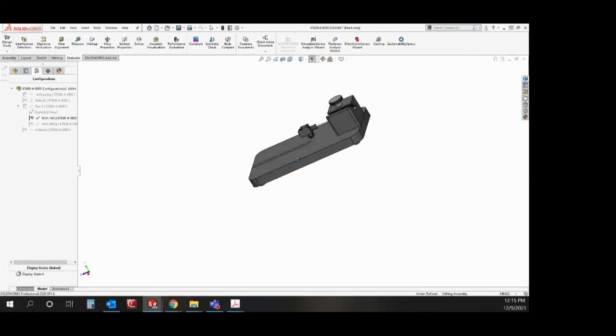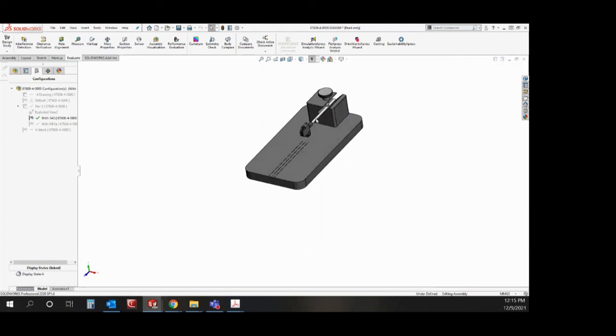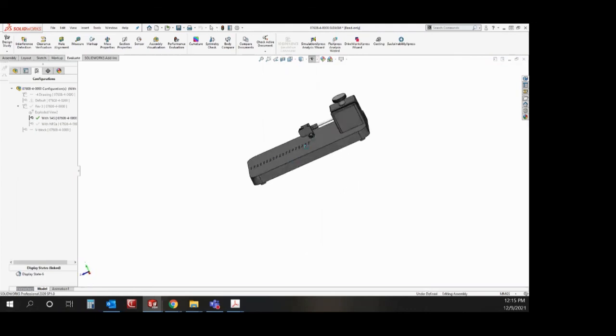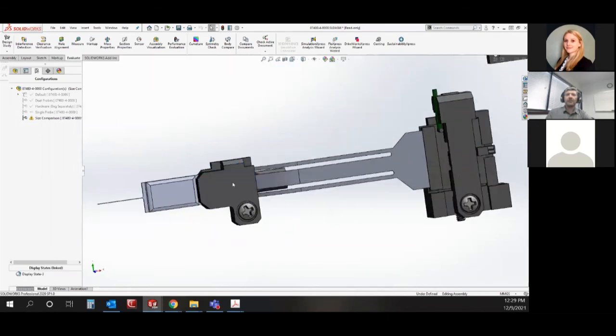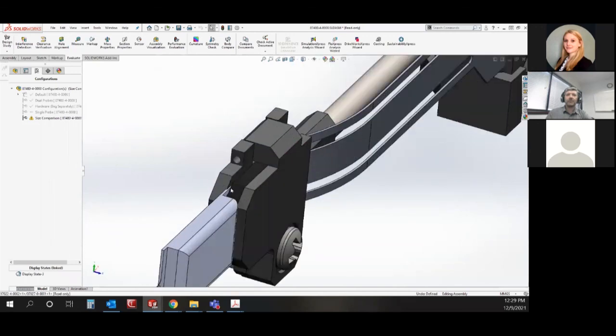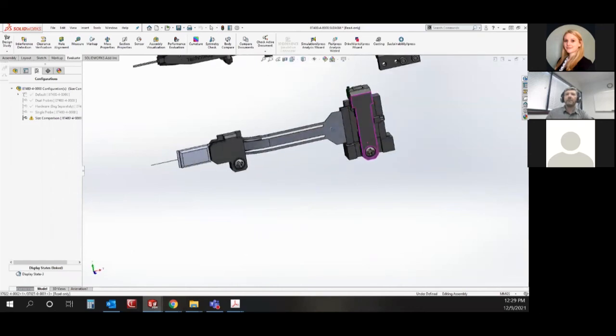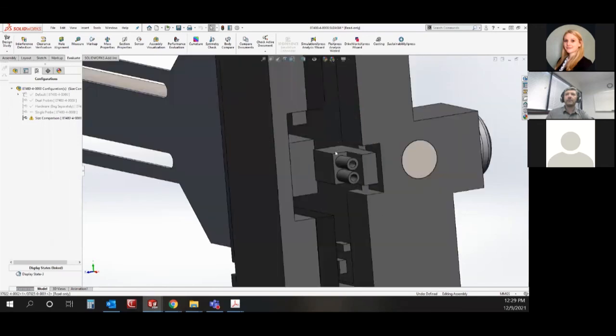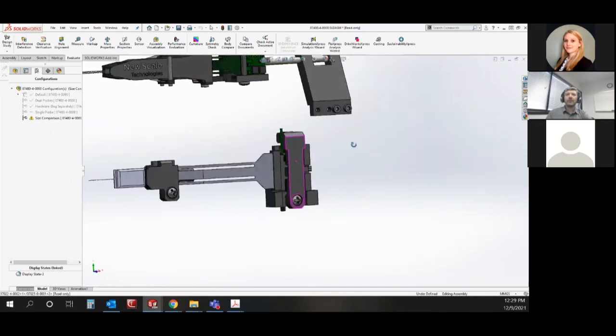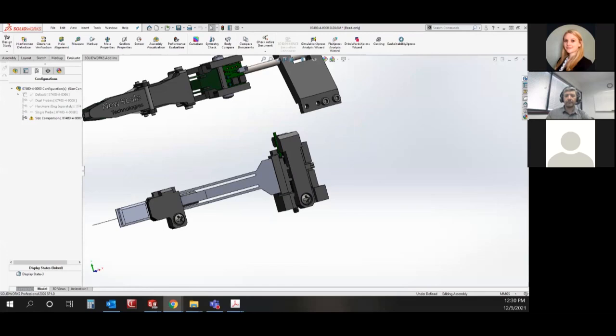The NeuroPixel 1.0 probes, we specifically recommend our 1A slim probe mount. I showed a quick glimpse of it attached to our alignment fixture here. This is the mount we would recommend for 1.0 probes, NeuroPixel 1.0 probes with no dovetail cap. And this probe mount here, our 1A slim would hold a single probe. Our 1A slim probe mount works with or without the dovetail cap because it grips by the probe PCB, where the dovetail cap is normally installed on the probe. This is what we would recommend for NeuroPixel's 1.0 probes. It also holds the head stage and mates directly with our MPM system and can be adapted to other systems as well.